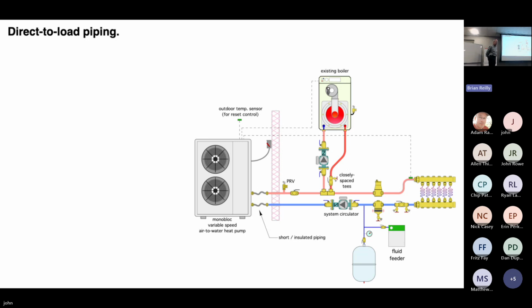That system needs sort of recharging. Like, I know because boilers have a fill valve for lost water. Yeah, typically you put in what's called a fluid feeder. There's a company called Axiom. And Axiom, they make these little 5-gallon plastic containers, and you put the mixture of 30% glycol water in there. And there's a little gear pump and a pressure sensor. And if it senses any drop in pressure out here, it just turns on that little pump and adds some fluid to the system. You would not hook up an automatic makeup water system. Right. Correct. If you had a leakage, over time you would dilute it.